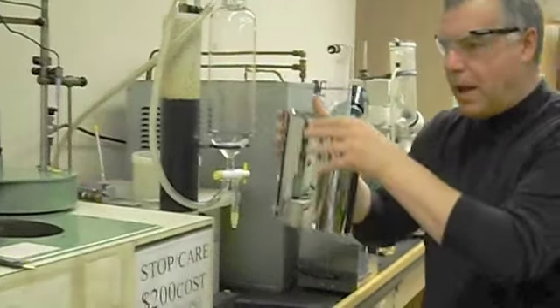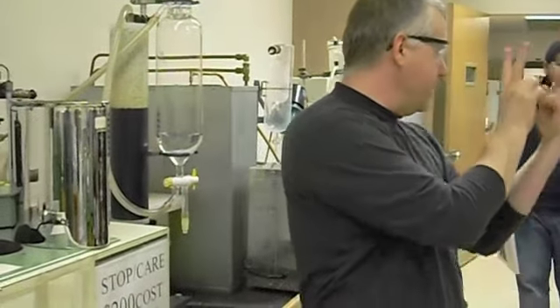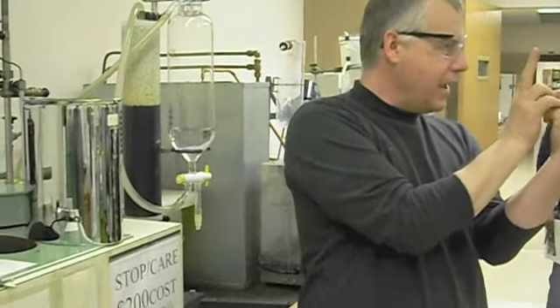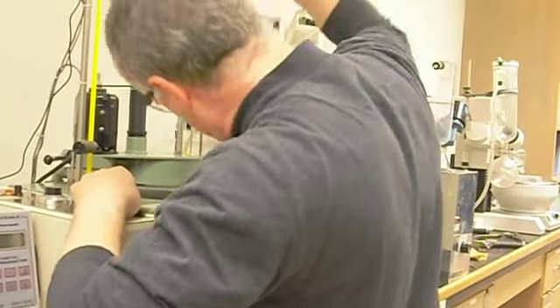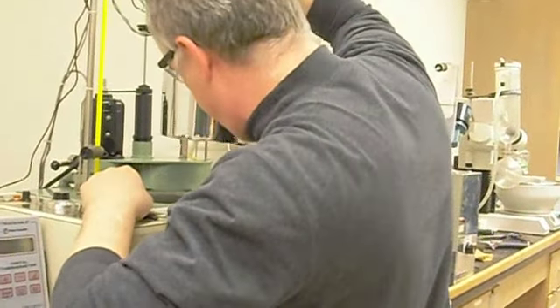And now we're good. So the next step is we're going to put this back into the calorimeter. Now, here's something I can't show you, but the bottom of this bucket has 3 little dimples. And there's 3 posts in here that correspond to the little dimples. Yeah, you can go in. And so when you send it, I don't think it's the end of the world if it's not matched, but it's nice. Alright, so I'm going to see if I can do that. Yep.